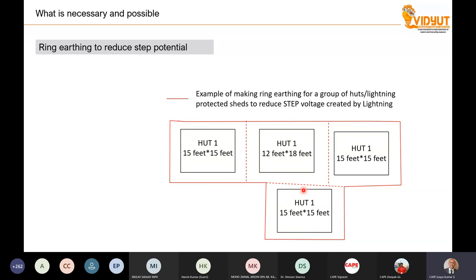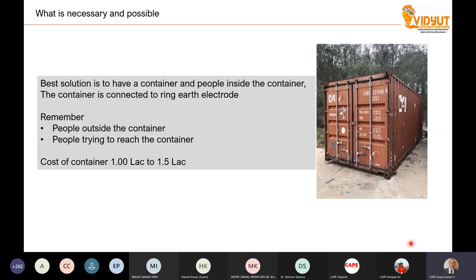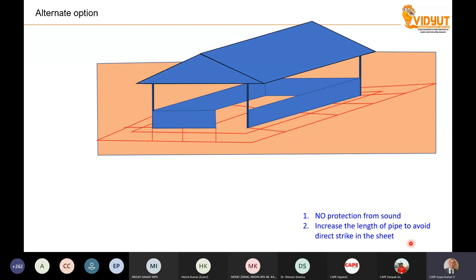Now, let me try to cut it short. What exactly is required for protecting rural places? The most important is step potential. In order to avoid step potential, the conductor which is buried in the soil shall be buried across or around the building as a ring conductor. A ring conductor limits the potential difference, and this is much better. The best way of protection is a container, but of course, a container is very expensive. You cannot put containers at several places and ask people to sit inside them during a lightning strike. This is very risky. One of the proposals is, instead of a container, probably at half of the cost of a container, a metal shed can be made.